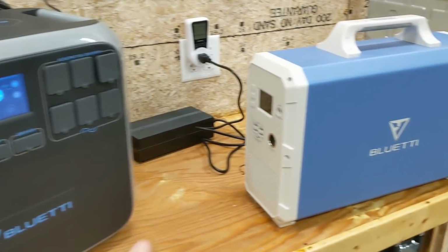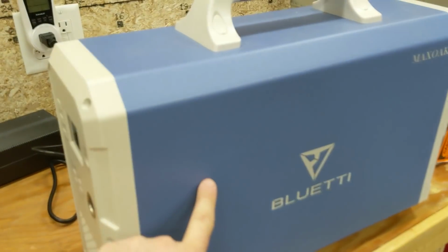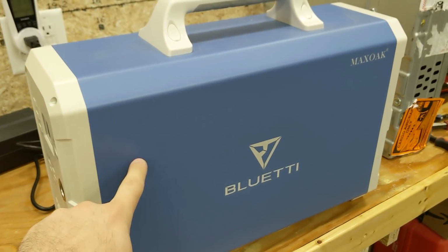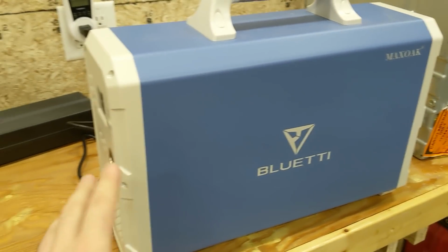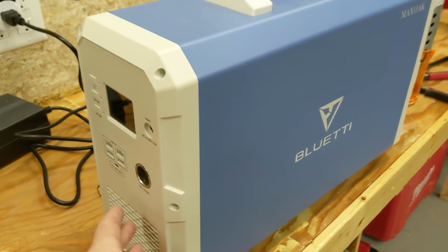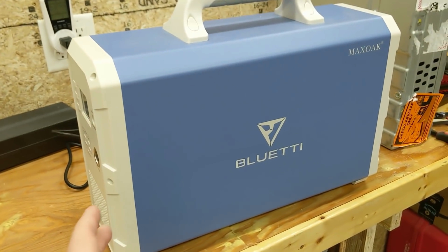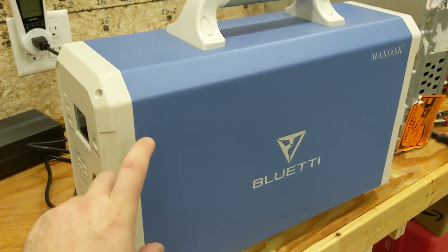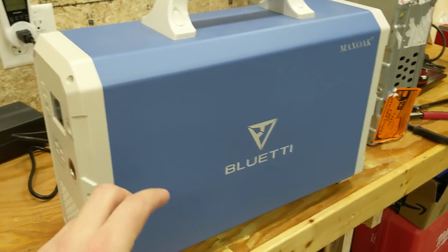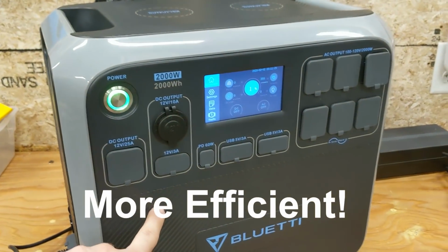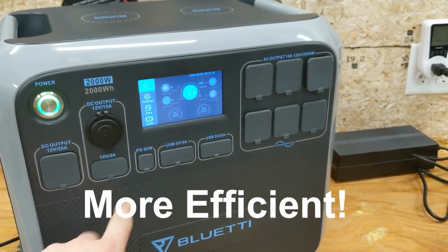Now the reason why I'm saying that is because when I tested this one, this is advertised as a 2.4 kilowatt hour battery, but we pulled 1.9 kilowatt hours out of it. The reason is that the BMS prevented us from using all of it, and then we also had the inefficiencies of the inverter. This one is advertised as a 2 kilowatt hour, and we pulled 1.8.